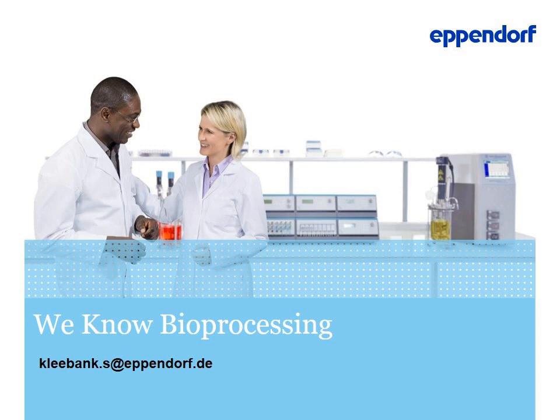Thank you. So the first question is, is the oxygen sensor polarographic or fluorescent? The oxygen sensor is polarographic. So we can insert this sensor into our non-invasive DO port, and it's not in direct contact with the medium because we have a silicone membrane at the bottom. And what type of sparger is being used, and what options do you expect will be available? The sparger that we used is simply a dip tube, so we don't use a sinter sparger.